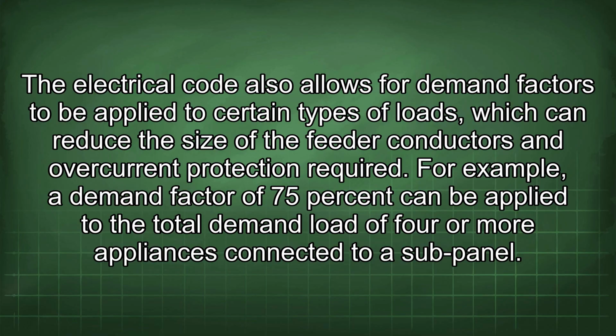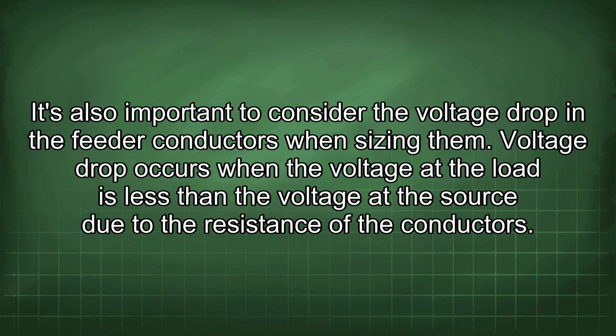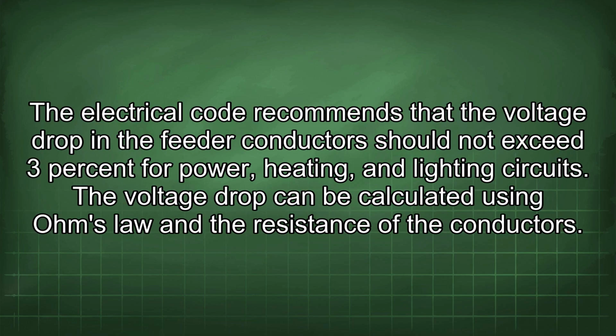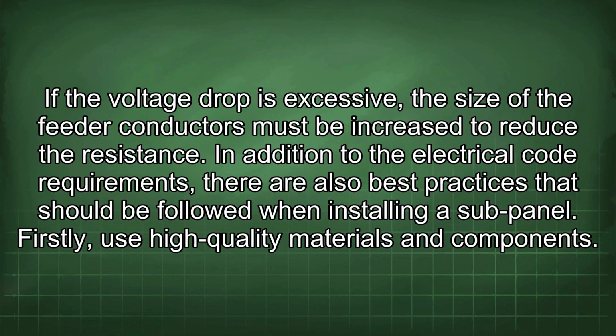connected to a sub-panel. It's also important to consider the voltage drop in the feeder conductors when sizing them. Voltage drop occurs when the voltage of the load is less than the voltage of the source due to the resistance of the conductors. The electrical code recommends that the voltage drop in the feeder conductors should not exceed 3% for power, heating, and lighting circuits. The voltage drop can be calculated using Ohm's law and the resistance of the conductors. If the voltage drop is excessive, the size of the feeder conductors must be increased to reduce the resistance.